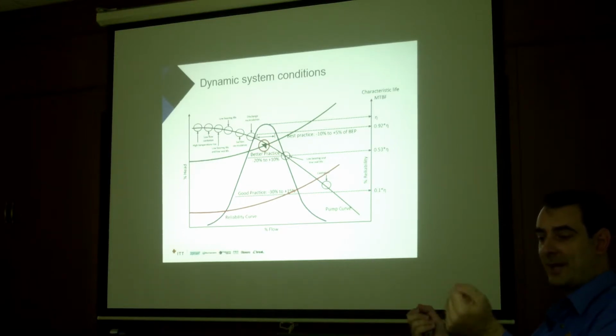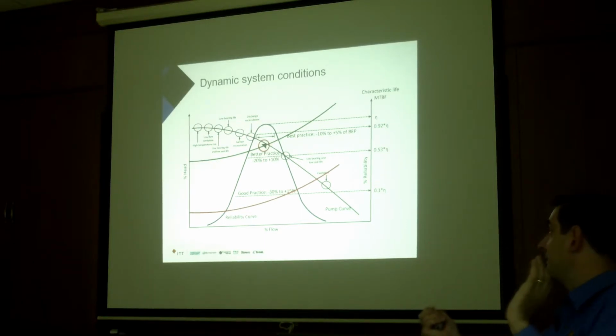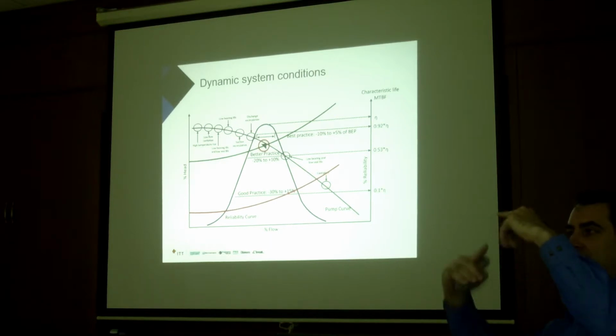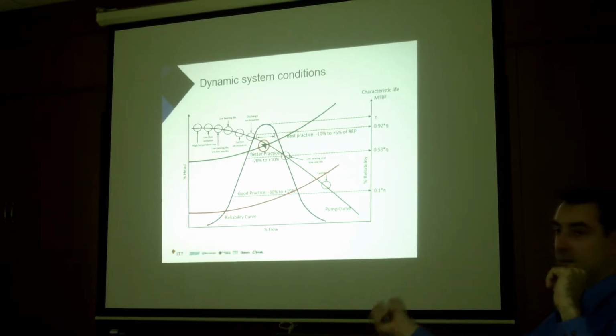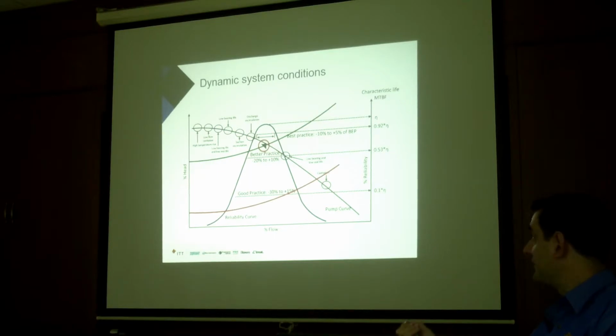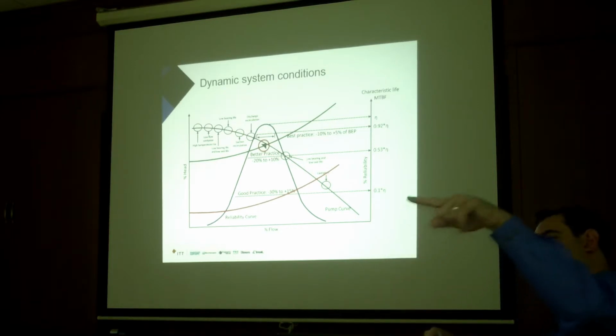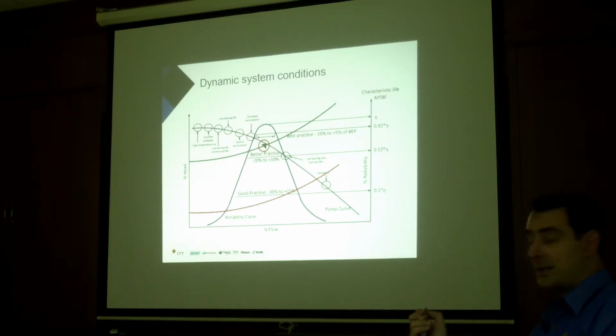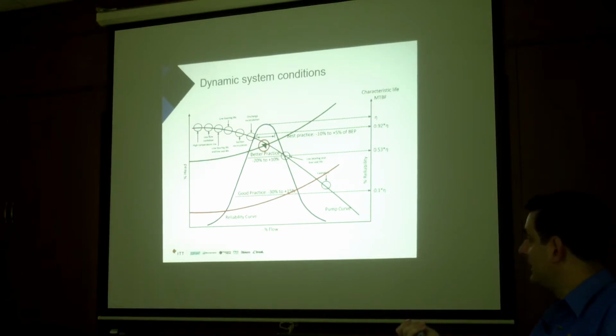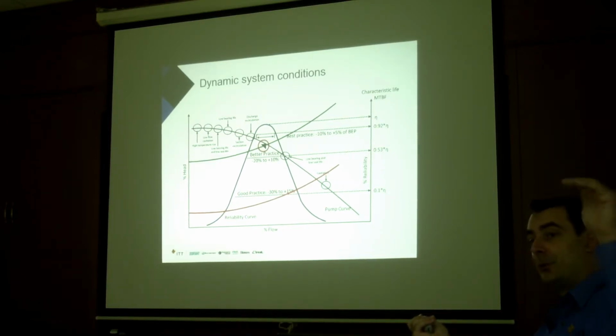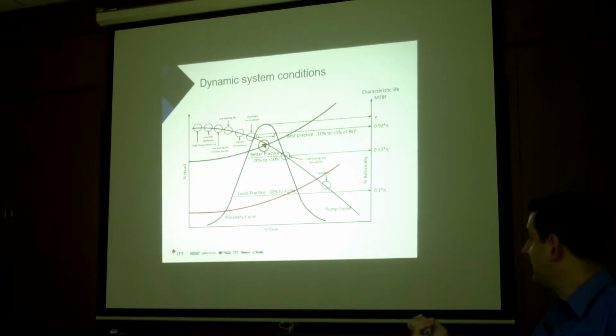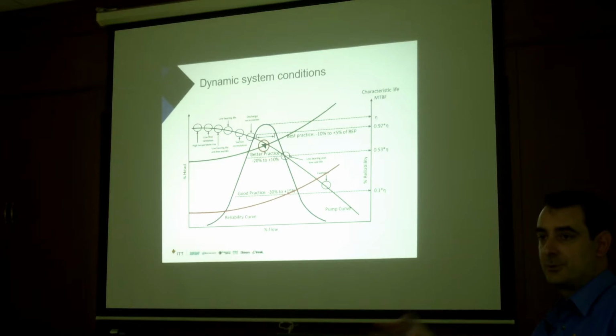Now if they throttle back and the flow goes down, the speed of the pump will just increase. And so eventually we'll get to a point where the speed goes up and the best efficiency meet at a perfect point where we're happy with it. Then in the future, as the tank level goes down, the speed will decrease, but we won't go past the best efficiency point. I can draw a map of it, but it follows. And as I explained to the customer, the worst time is the red line, when the tank is full. So it's the first time you operate, so you push here. And then from then on, the pump speed will do the rest.